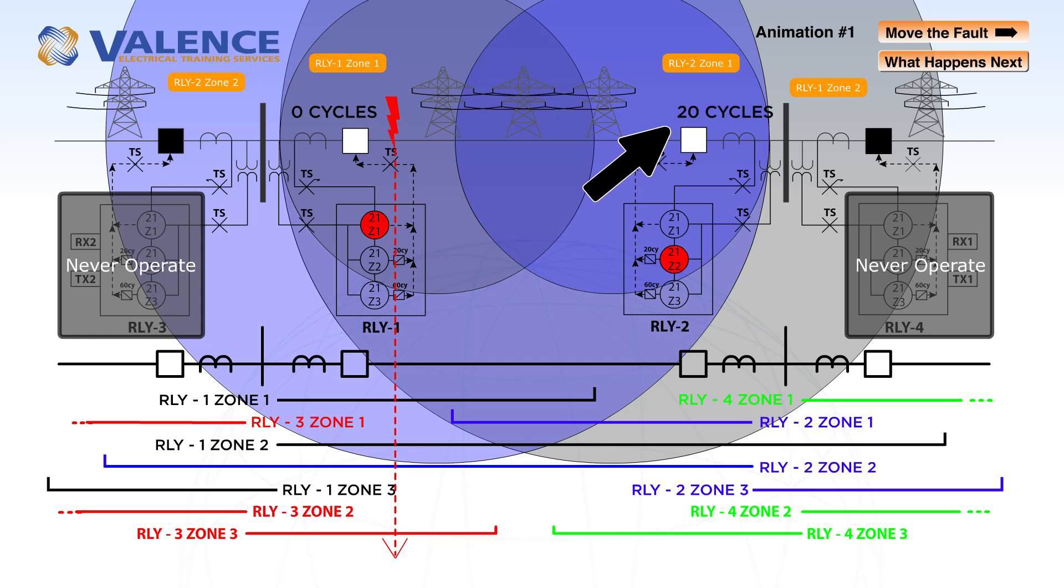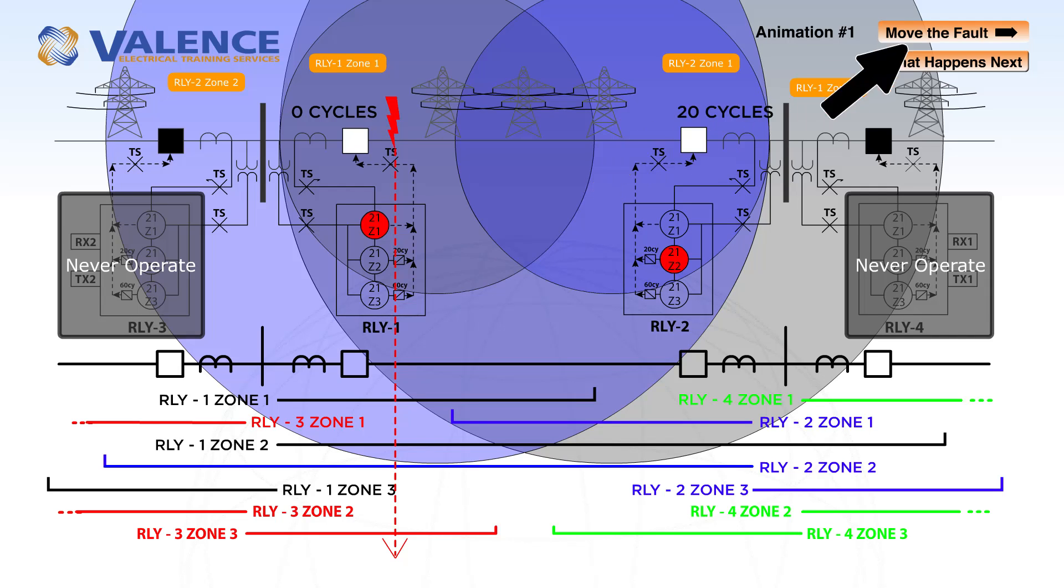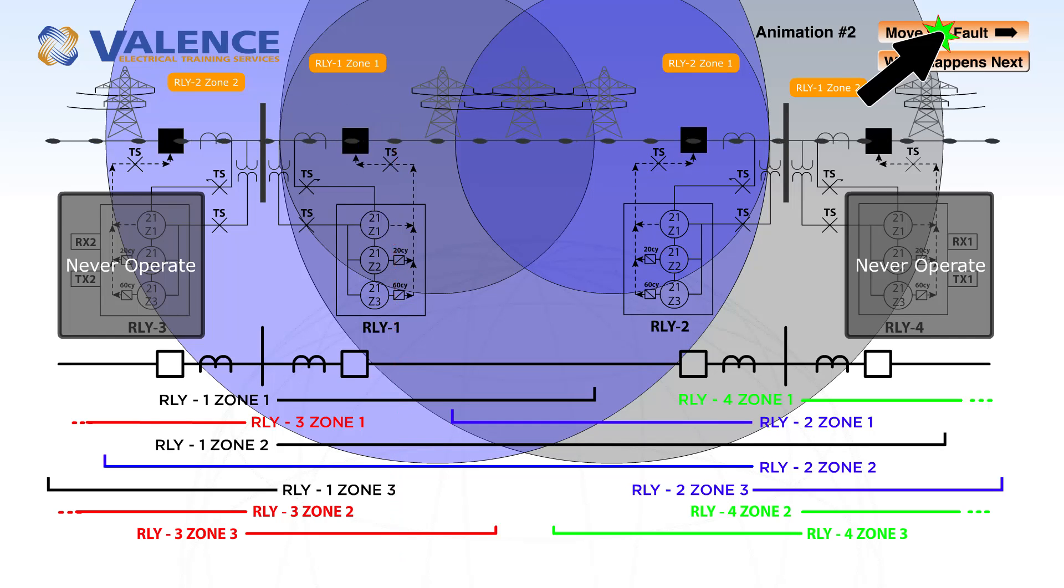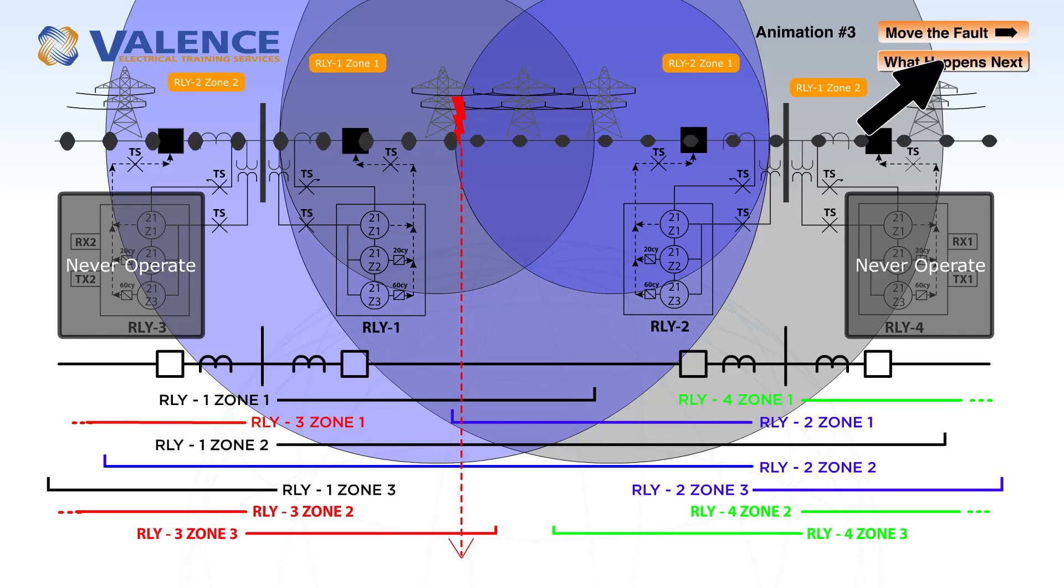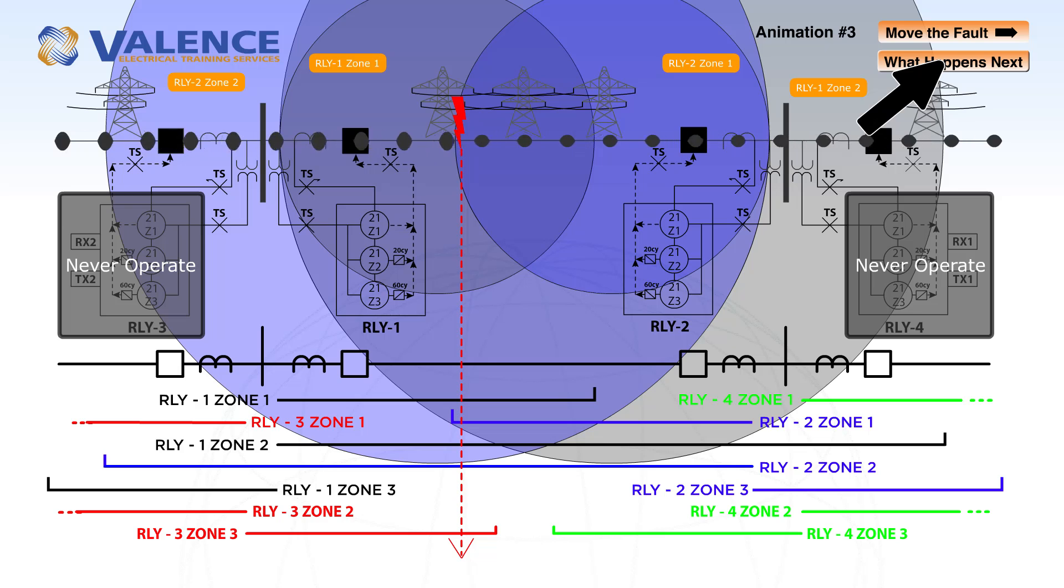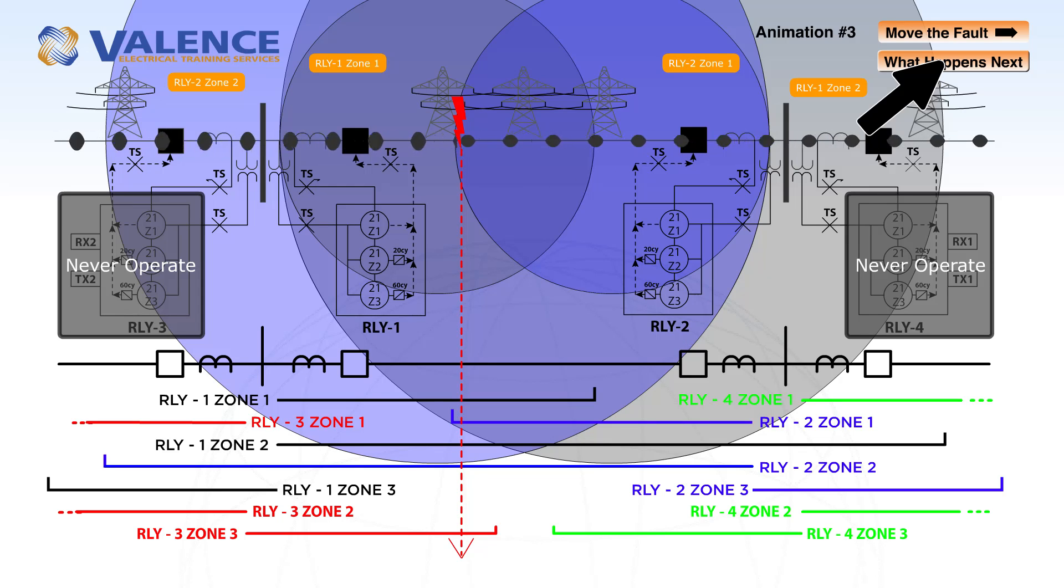When you're doing an end-to-end test, you simulate a fault on one side of the protection zone to make sure it operates correctly, and then you move to the other side of the protection zone to see what happens when the fault location changes.